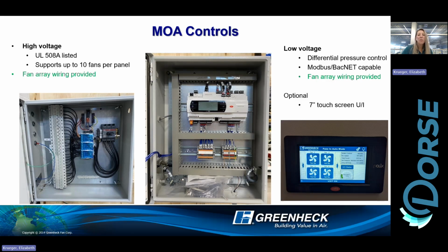This is just a quick overview of what our controls are looking like here. So again, that high voltage panel, high voltage is landed, and I don't see our inlet on this, or the inlet where they're landing the voltage, but basically voltage landed to one point inside of this panel, and then each of these distributes the needed power to each fan. In that same wiring, this is our control panel here with a Carel controller. In that same wiring, we will also have the 0 to 10 signals that each fan would require. And then we do offer a touch screen as well.